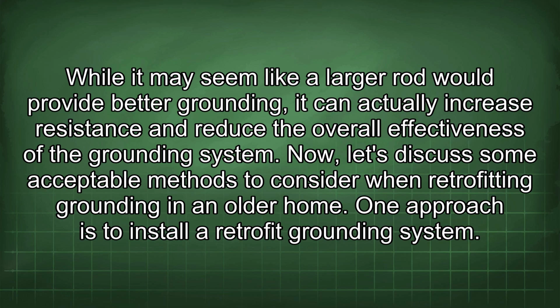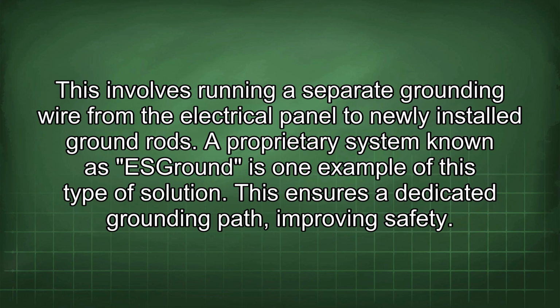Now, let's discuss some acceptable methods to consider when retrofitting grounding in an older home. One approach is to install a retrofit grounding system. This involves running a separate grounding wire from the electrical panel to newly installed ground rods. A proprietary system known as ESGround is one example of this type of solution. This ensures a dedicated grounding path, improving safety.